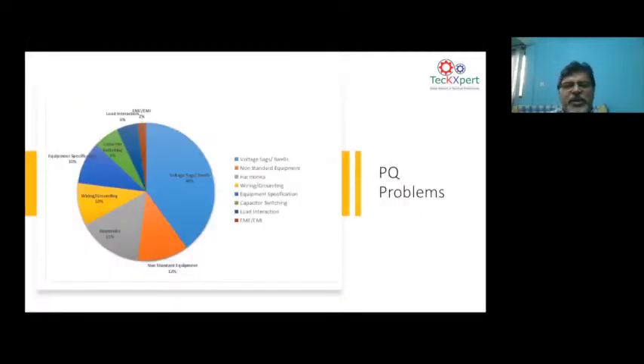Again, when it comes to power quality problems, we look into this pie chart. What is very important is that you can see harmonics. In the majority of cases, a direct harmonic related problem may not be more than 15 to 20%. But of course, if your wiring and grounding is not okay, then a lot of problems can happen. Harmonics can get amplified. Equipment can fail. A harmonic can be the cause of the problem, but because your wiring and grounding is not okay, the harmonics can create the failure of an equipment.